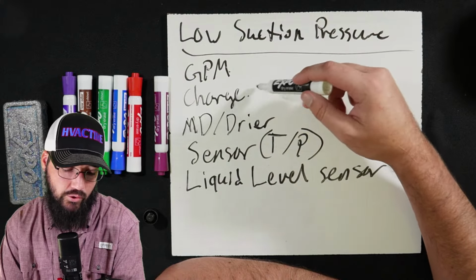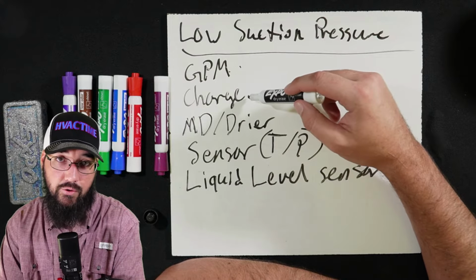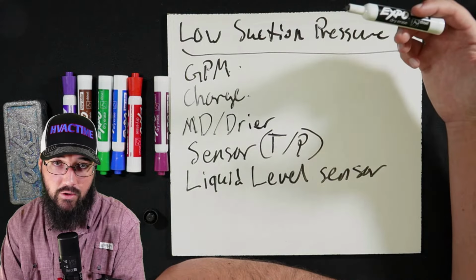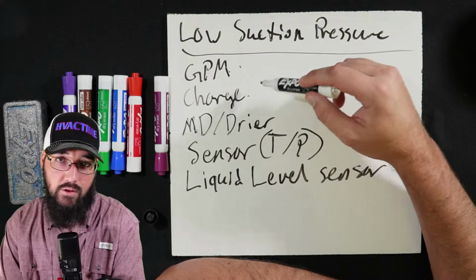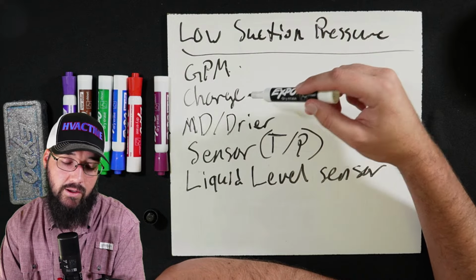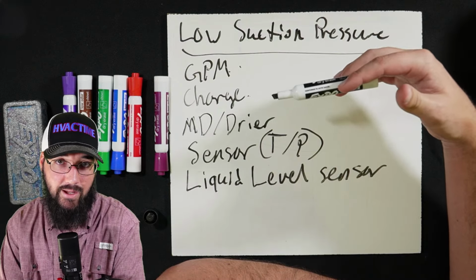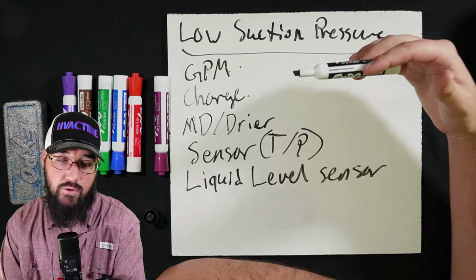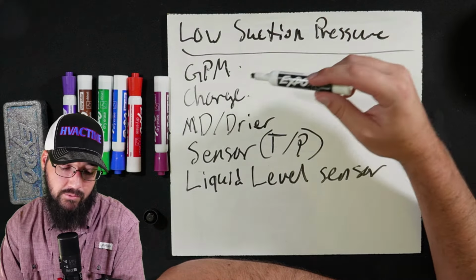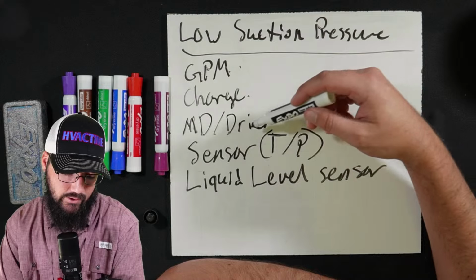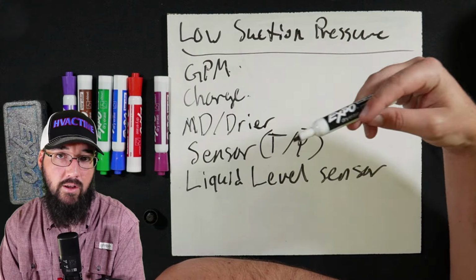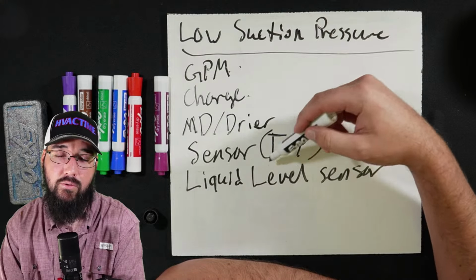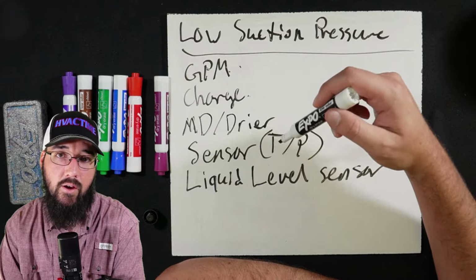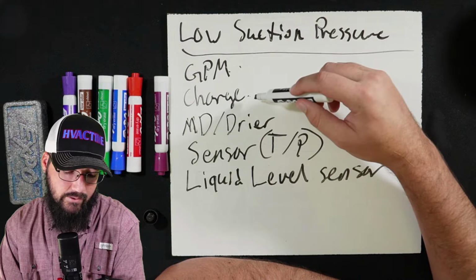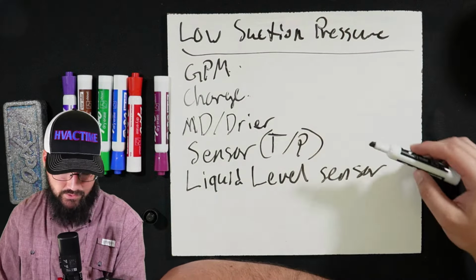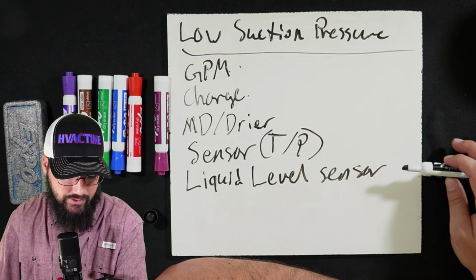So that's one of the early areas. Get our flow right, make sure our charge is good. If we have a good charge and we have a load, I stress the load part because if we have a really low load condition, you might see low subcooling at that state, right? If that is true, don't just assume it's a charge issue. It could just be a load problem. But if you have load and the GPM is good, then we're going to come back to one of these other conditions. It's not likely a charge problem. It's probably a sensor or maybe the metering device, something along those lines are far more likely to be true. Yeah, I would say these are the main things I would want to be looking at.